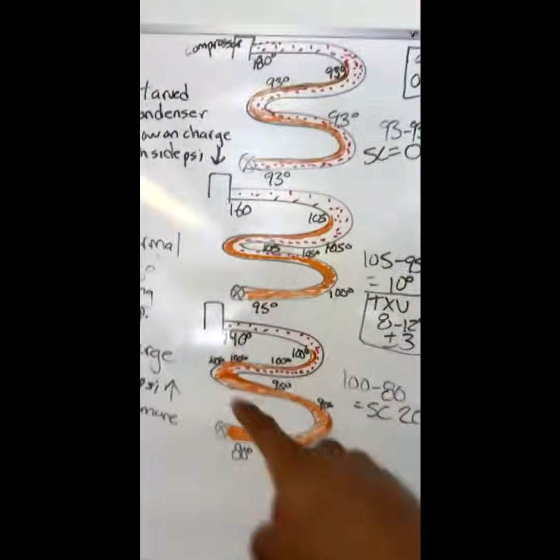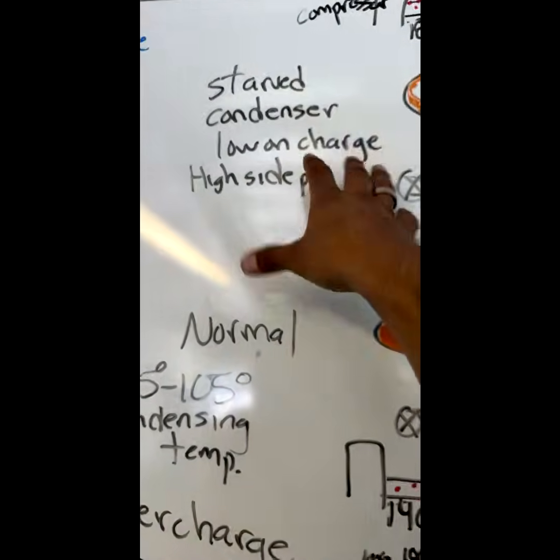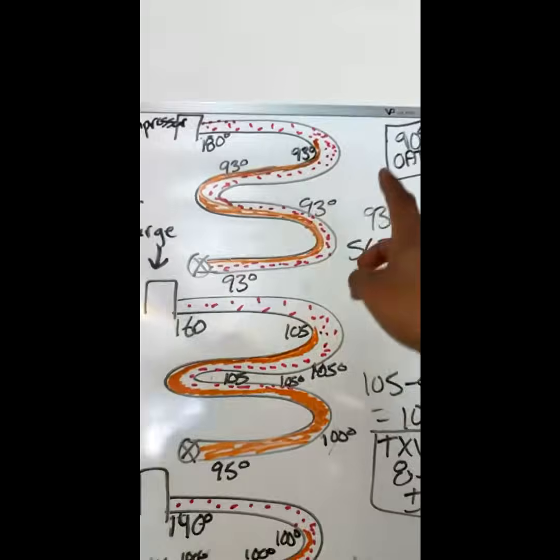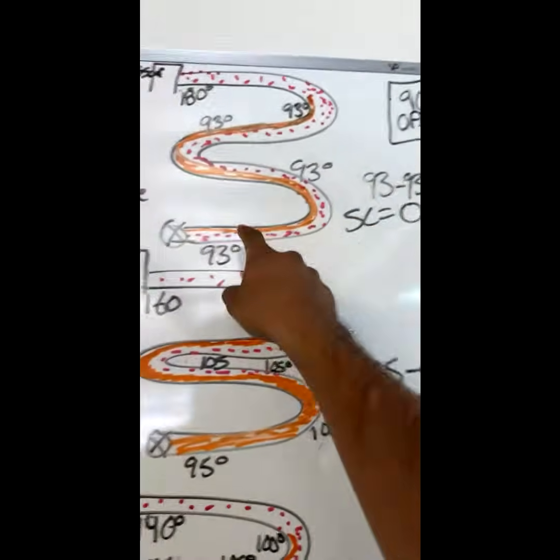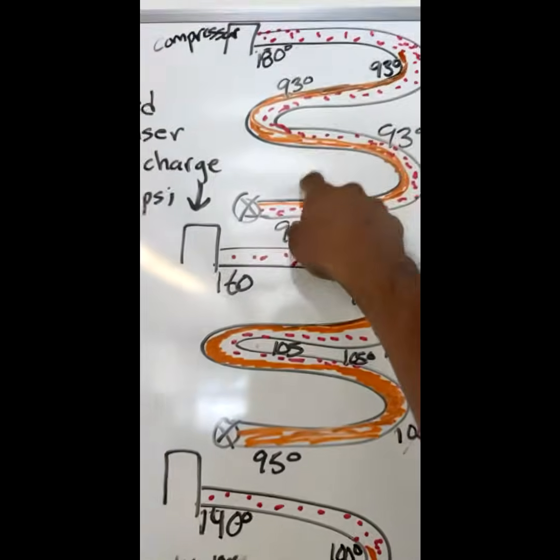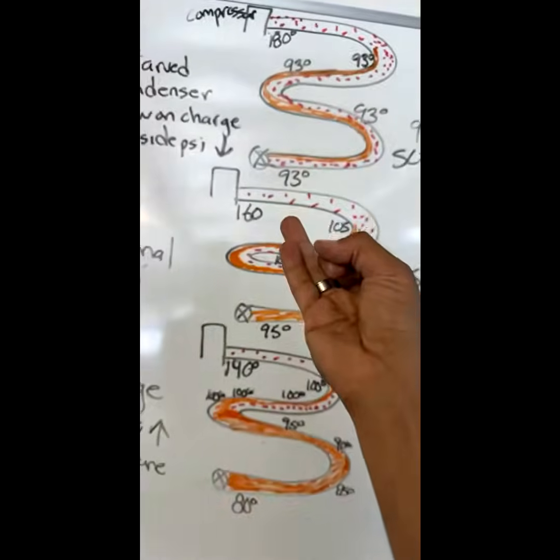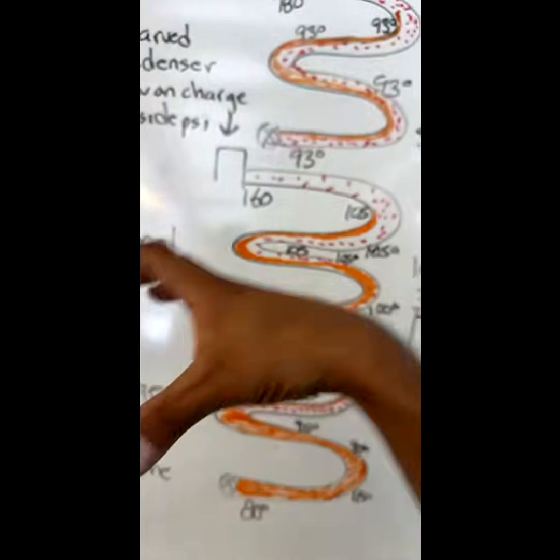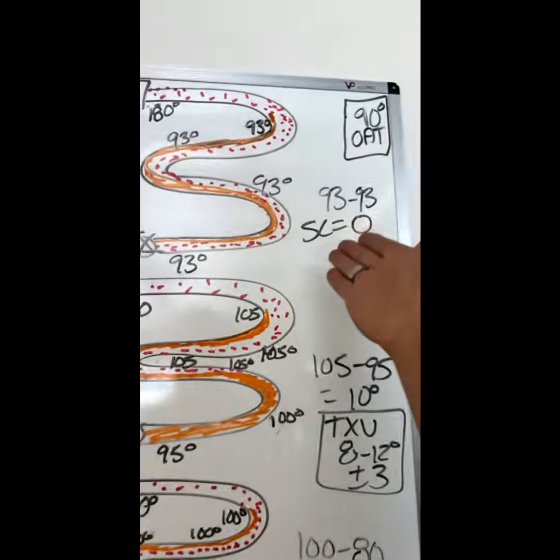I want to show you guys what I did today. I'm not the best at drawing, right? Actually, I had erased some of it. But I talked about subcool today. When you have a low subcool, you have a starved condenser. It's low on charge, and a lot of people don't understand. But the condensing temperature of your system, right? High-side pressure converted to temperature. That one actually has to be a lot higher than your ambient temperature, so you can reject more heat and get more liquid.